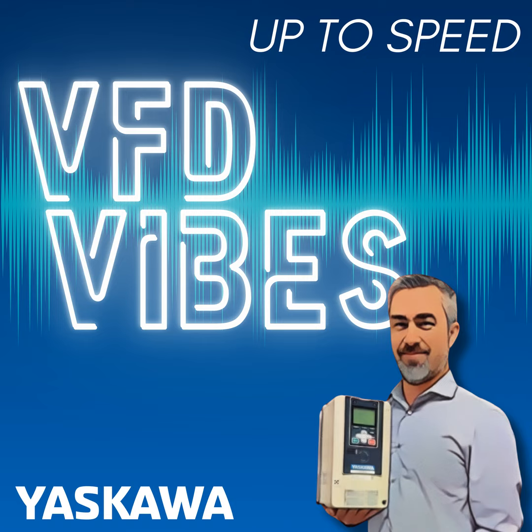You can actually power up the brains of the drive via USB cable to a mobile phone or computer and program before you have mains power. So you could use this simulator to go through a setup before the drive arrives. And then before it's even installed, you could have that program copied into the drive. Then when power is applied at the actual time of commissioning, it's just time to test it out. It's already programmed and ready to go.